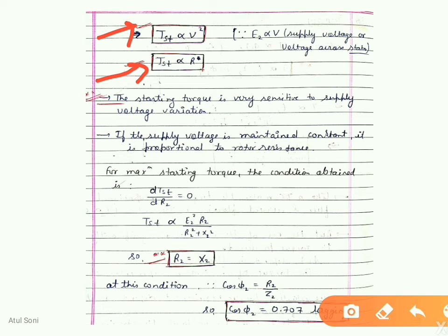To find the condition for maximum starting torque, we differentiate the starting torque equation with respect to rotor resistance and set it equal to zero. This gives the condition R2 = X2: when the rotor resistance is exactly equal to the rotor standstill reactance, the rotor develops maximum starting torque. At this condition the power factor is 0.707 lagging.